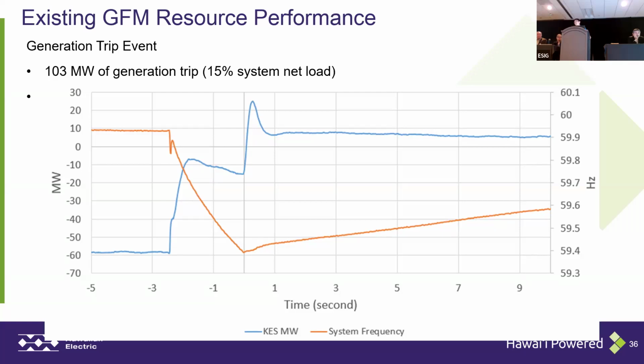Immediately after the generation trip, there's no system fault, so this is a pure generation trip. We see very strong response coming from the KES facility. At the very beginning we thought, oh, that's probably triggered FFR. But when we align the megawatt response with the system frequency, it actually is not. It's a grid forming response to this generation trip. And we do see this immediate response from the KES facility help reduce the frequency change.